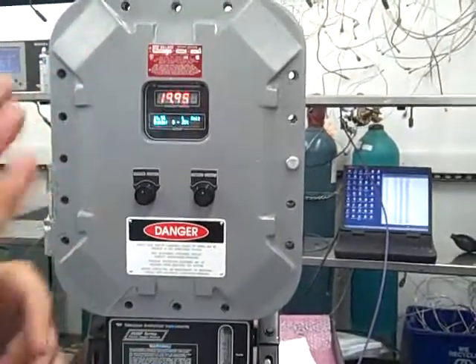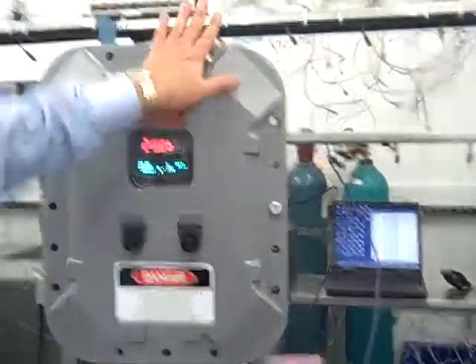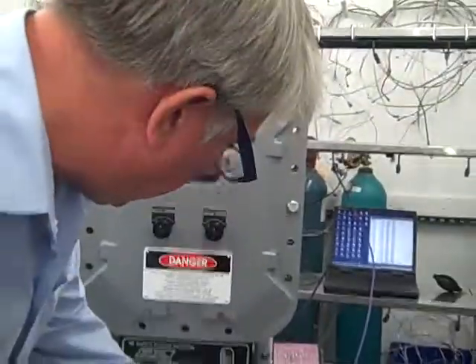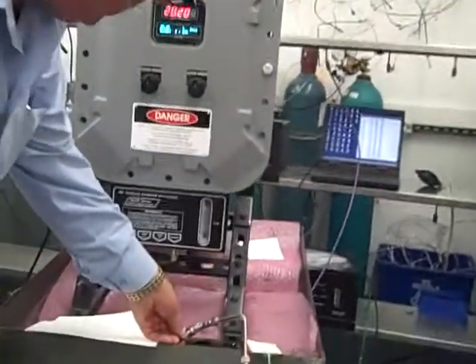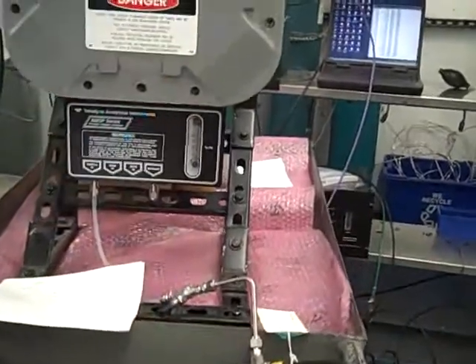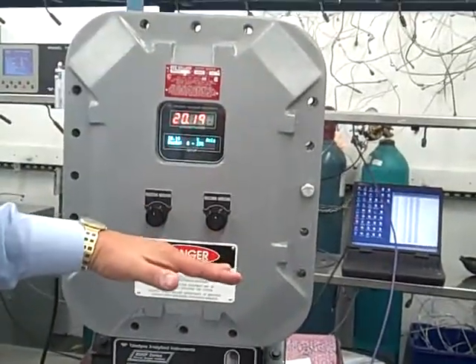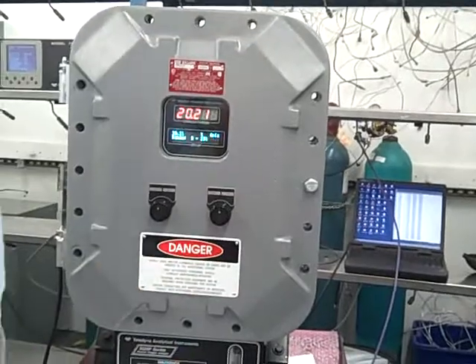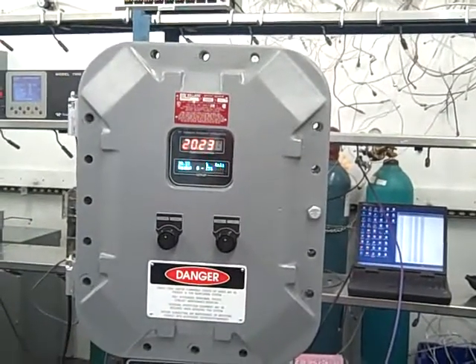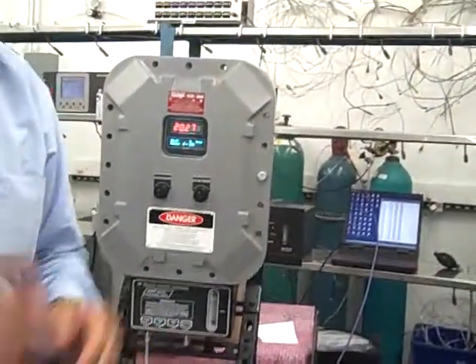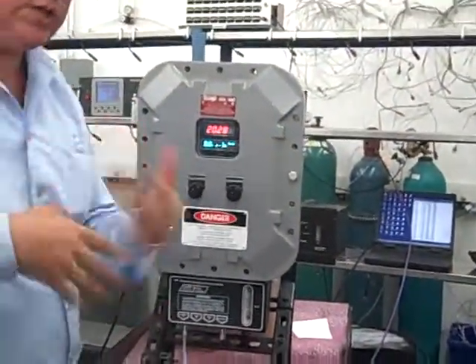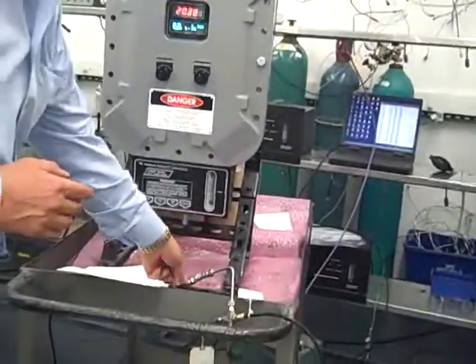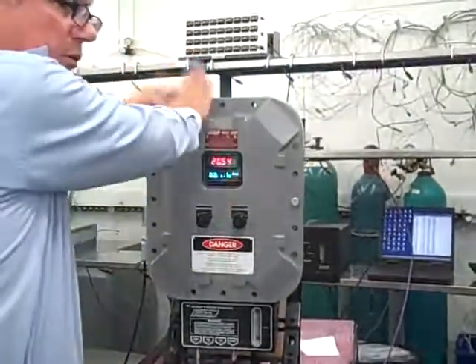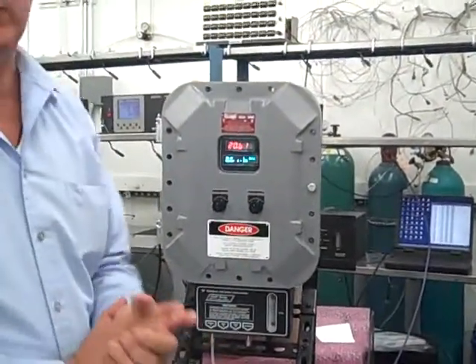So if you have a leak in your sample delivery system, or perhaps inside the unit, one way you can tell that is by reducing the flow. And you can see now I'm reducing the flow. And if the reading goes up with lower flow, and the reading goes down with higher flow, in many cases that's a leak, and that's really useful for checking out your 3020T analyzer to make sure you've got a tight system. So if you are seeing reading variations, that's the first test you want to do, is the flow sensitivity test.